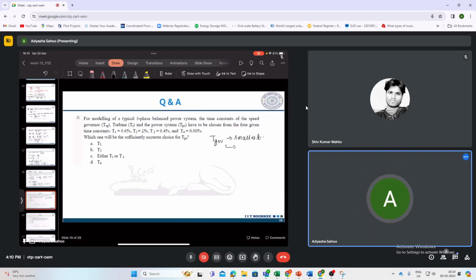So that is in the order of 0.8, something like that. Then after that, your turbine. So it is around 0.3 to 0.5 second. And for the power system, T power system was nothing but your 2H F naught by D, right? And that is in the order of 10 to 15 or 15 to 20 seconds. So you can see that your T power system is much greater than your turbine and governor. So you get this relation here.